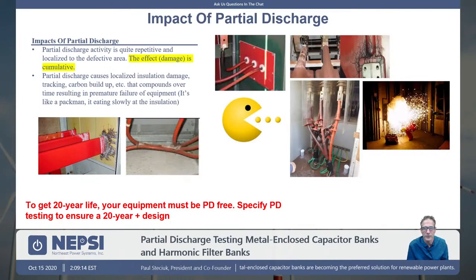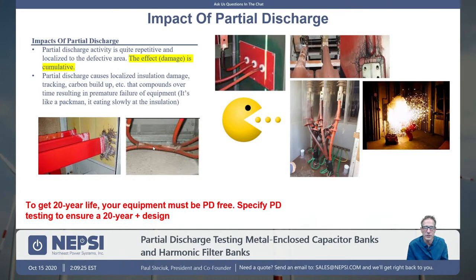So you have a high voltage area, you have a pass through. It's very common that that's where partial discharge will occur. The other, here we have cable, you can see the white on the outside, and this is a very common practice that people have. You can buy 15 kV jumper cable, and 15 kV jumper cable is not grounded. It doesn't have a ground shield on it, and therefore the voltage stress profile within the cable is not evenly distributed around the cable. As a result, when you take that cable and rest it at ground potential, you have localized stresses, and therefore you have partial discharge, and it results in damage to the cable. And over time, it will eventually fail.